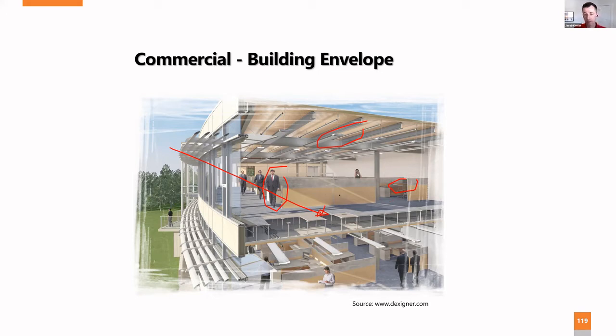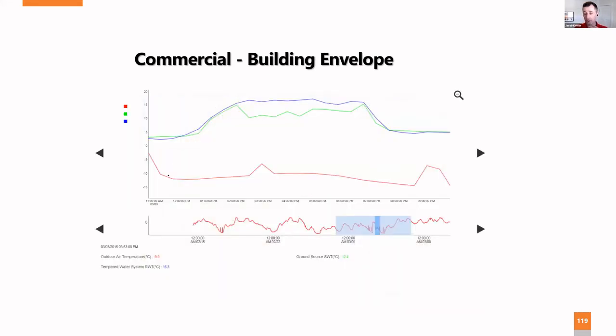So the Mosaic Center, which was a 30,000 square foot building, for example, this graph shows they had just moved in. It was February, and this red line shows the temperature. So it was between -10 and -15 outside. The green line shows the temperature of the water coming from the ground loop, and the blue line is the temperature of the water going back to the ground loop. And so what we can see during the afternoon in February, as soon as you see the sun hit that south wall and those solar gains come in, we are rejecting heat to the ground loop. This building is rejecting at -10 to -15. And that was, the building was only about 20% occupied.